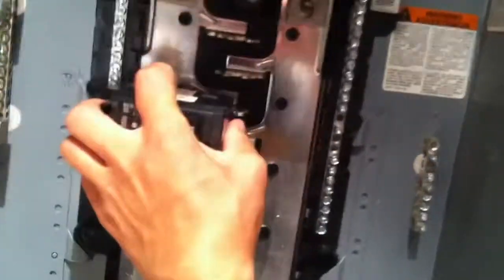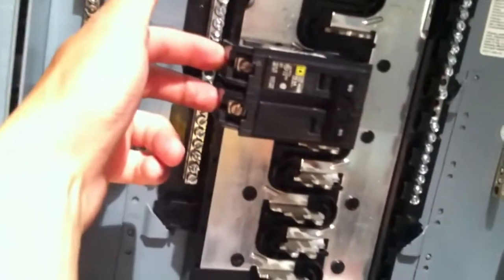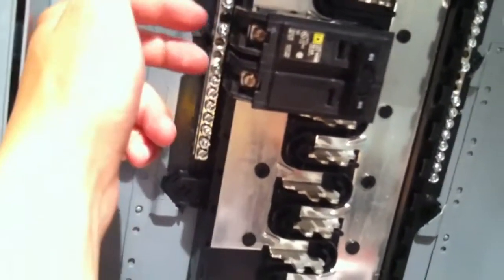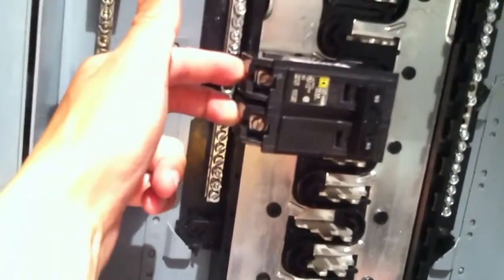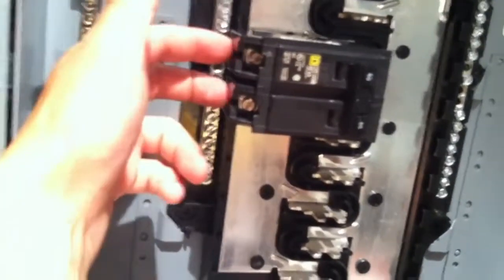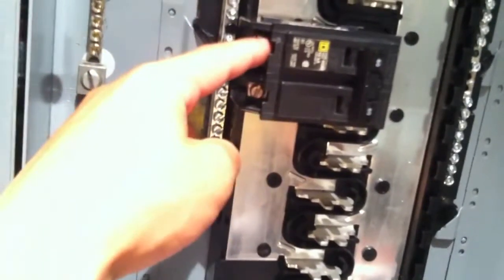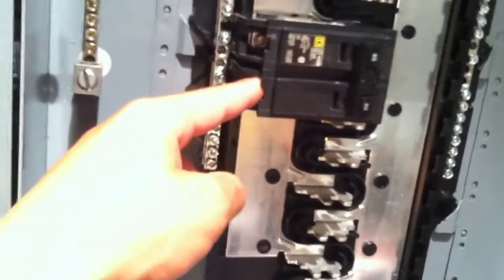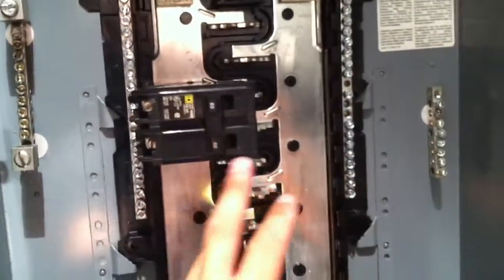If it looks like a little breaker like this, with those little screw terminals, whatever is coming into those—if it's a main breaker—you will never shut those screws off. No matter which way this switch is flipped, no matter what's going on on this side, there's nothing you can do to shut off those screw terminals.